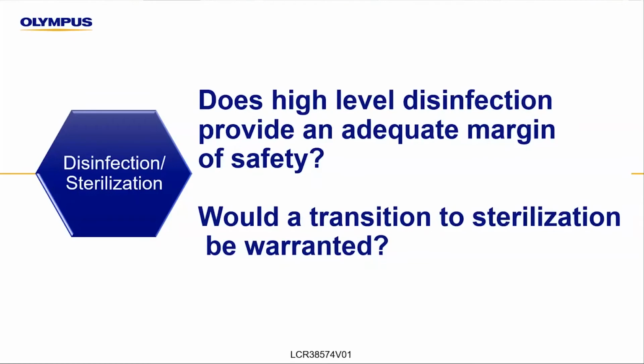But if you think about it, high-level disinfection is expected to provide a 6-log reduction in CFU and theoretically should kill any type of microbe other than high levels of spores. And sterilization, on the other hand, also should provide a 6-log or more reduction of organisms and should kill high levels of spores. It basically should kill all potential microorganisms that could possibly be in the scope. So really the difference is the ability to kill spores between those two methods. And I would agree that if it's done properly and with a quality system approach, for some of the GI scopes, I think it's still a very valid method of reprocessing scopes.